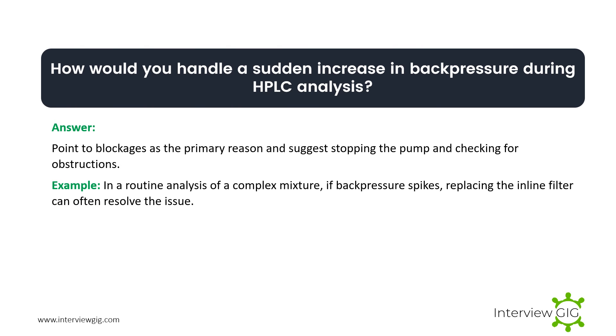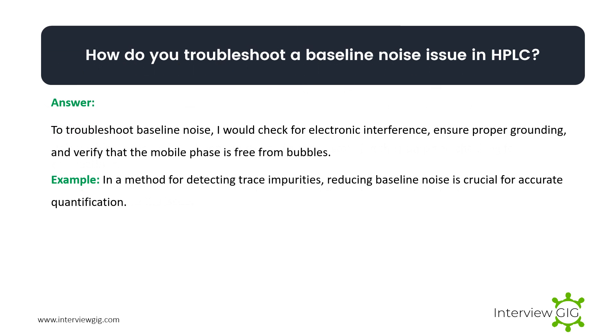How would you handle a sudden increase in back pressure during HPLC analysis? Point to blockages as the primary reason and suggest stopping the pump and checking for obstructions. Example: in a routine analysis of a complex mixture, if back pressure spikes, replacing the inline filter can often resolve the issue.